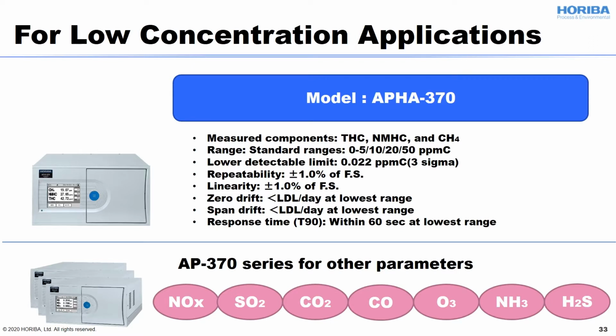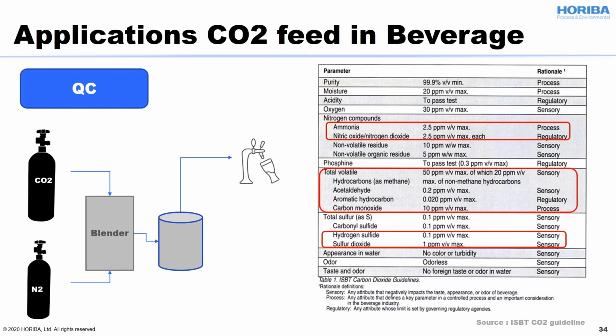HORIBA has an AP370 series other than APHA-370. Each analyzer has individual measurement parameters. All models can measure very low concentration. Other than total hydrocarbons, the AP series can measure NOx, SO2, CO2, CO, O3, ammonia, and H2S. So let's take a look at this application one more time. As the ISBT quality guidelines show on the right side, there are a couple of gaseous components. The HORIBA AP series can measure those parameters like ammonia, NOx, total hydrocarbons, H2S and SO2.